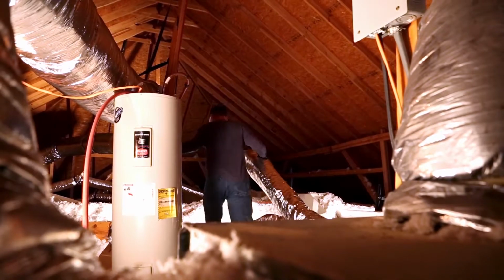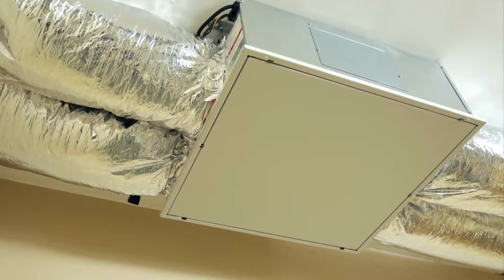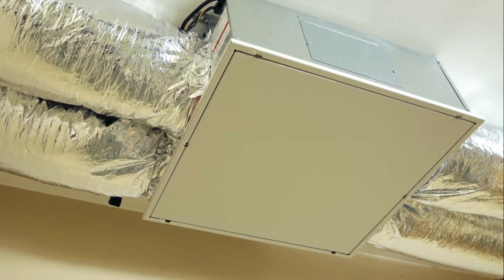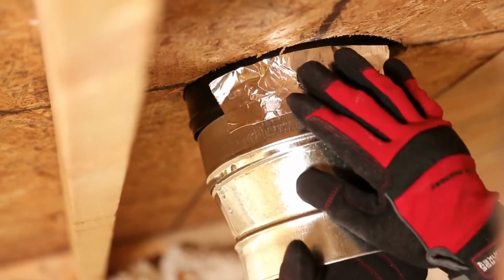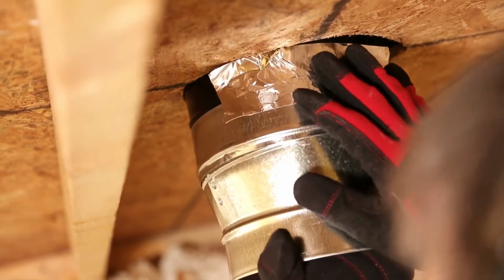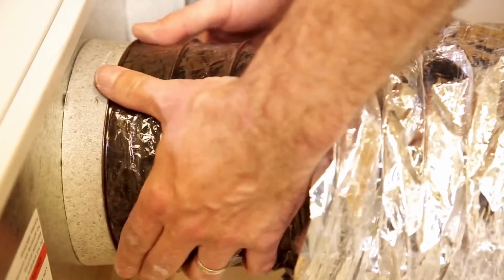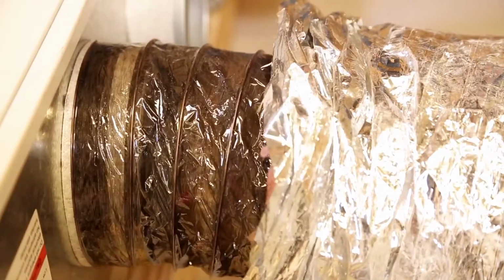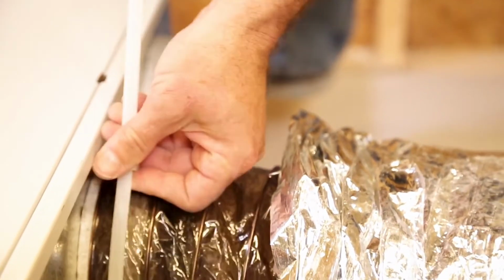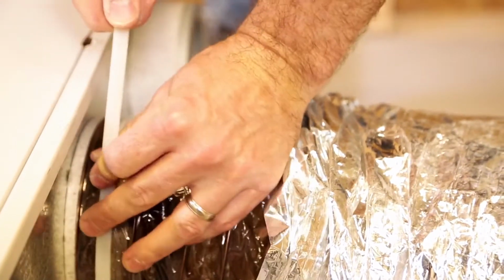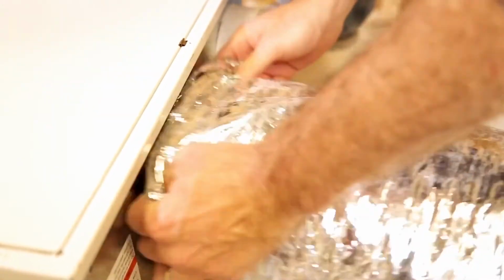Now it's time to install ductwork. All ports on the unit should be connected to 6-inch ducts. However, you can connect to larger ducts using appropriate transitions. When attaching insulated ductwork, pull back the insulation to expose the flexible duct. Attach the flexible duct to the port using a tie wrap. Pull the insulation and vapor barrier over the joint.